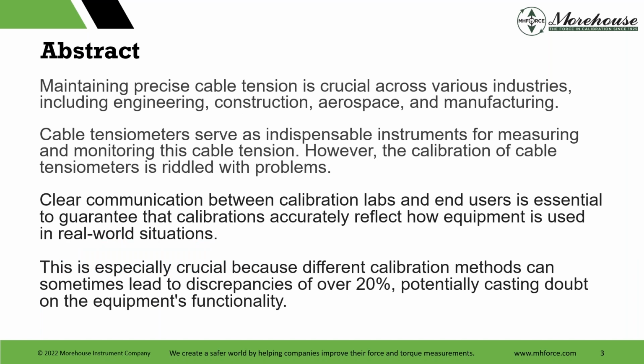And so, abstract: we're calibrating cable tensiometers. You're here because you're either doing it or you want to learn more about it, or maybe somebody has people saying, hey, can you calibrate these? They're not that difficult to calibrate, though there are a lot of nuances, and there are a lot of people making equipment out there that's really not suitable for the calibration of tensiometers. And they're used everywhere: engineering, construction, aerospace, manufacturing. Kind of indispensable, right? If you want to check tension on a cable, that's what we have.